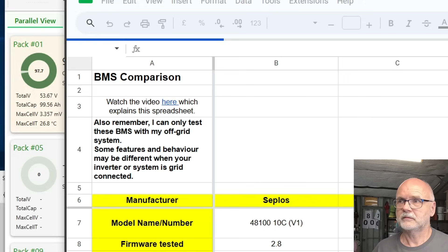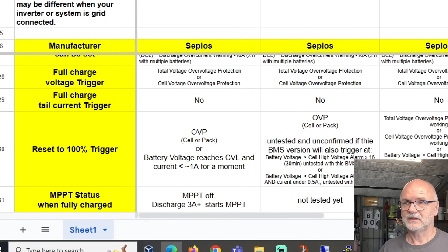But maybe they have also fixed the other trigger to 100%. If we have a look in the BMS comparison table under Seplos version 3, the reset to 100% trigger is either the total voltage over voltage protection, confirmed working, or cell over voltage protection, also confirmed working. And then there's also battery voltage higher than the cell high voltage alarm times 16 for 30 minutes.